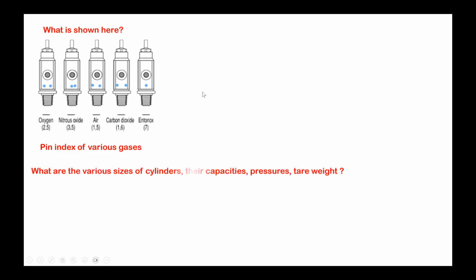Different pin index systems for different cylinders, for various gases. Can you identify what are all the pin indexes of these gases? First is oxygen. Second is nitrous oxide. Third one is air. Next one is carbon dioxide. Last one is entonox. Okay, so oxygen, nitrous oxide, air, carbon dioxide, and entonox. So the position is 2,5 for oxygen, 3,5 for nitrous oxide, and 1,5 for air. And carbon dioxide is 1,6 and entonox is 7.